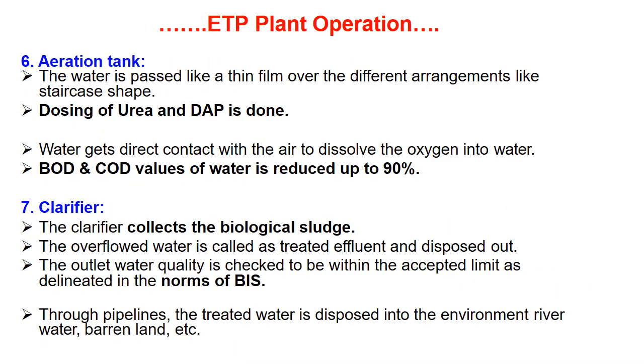Continuing plant operations — number six is the aeration tank. Water is passed as a thin film over staircase-shaped arrangements. Dosing of urea and diammonium phosphate is done. Water gets direct contact with air to dissolve oxygen into the water. The BOD and COD values of water are reduced by up to 90%.